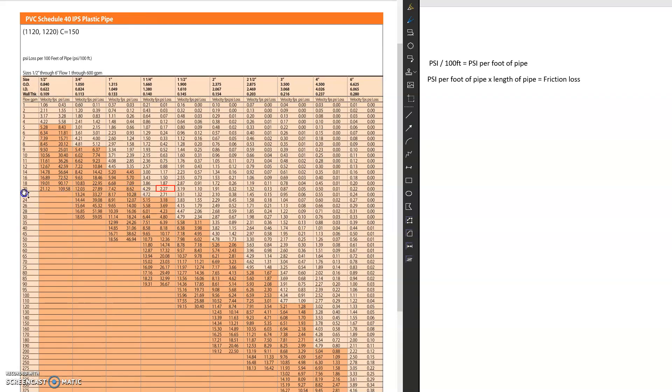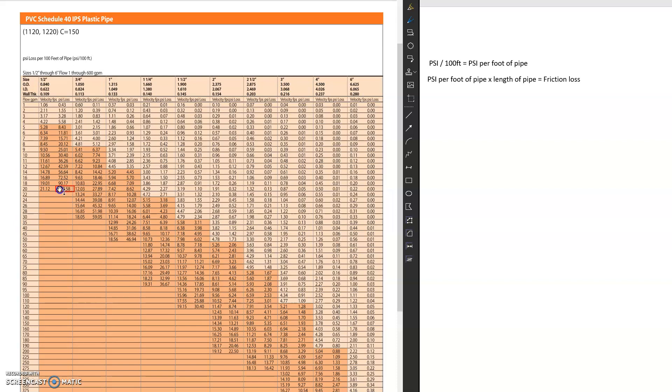Now let's say that same 20 GPM, I had half inch pipe. Look right here on the half inch pipe, that's 109.58 PSI that we lose for 100 feet of half inch pipe. You can see on the column that especially as the flows get bigger, it's not just a linear fashion, but a lot of these it gets into exponential factors of how quickly the pressure loss increases as you increase the flow, especially in smaller diameter pipes.